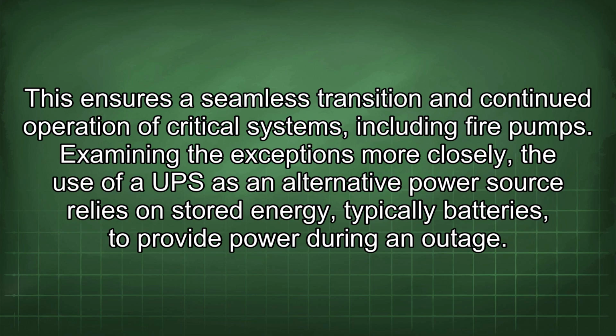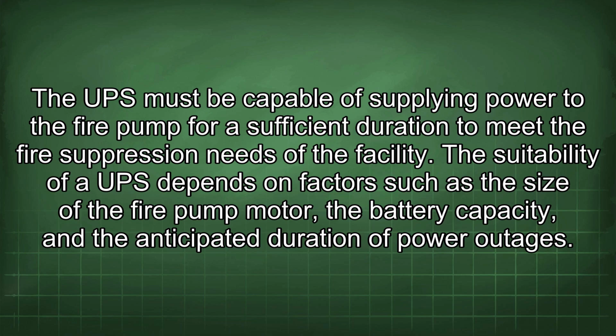Examining the exceptions more closely, the use of a UPS as an alternative power source relies on stored energy, typically batteries, to provide power during an outage. The UPS must be capable of supplying power to the fire pump for a sufficient duration to meet the fire suppression needs of the facility. The suitability of a UPS depends on factors such as the size of the fire pump motor, the battery capacity, and the anticipated duration of power outages.